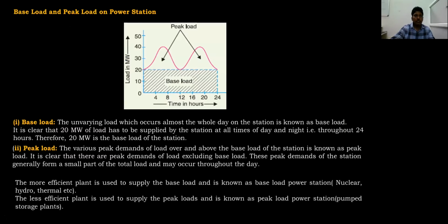And next we are coming to base load and peak load power plants. Base load on a power station means the unvarying load which is there from 0 to 24 hours in a day. For example, here from 0 to 24 hours we have a load curve. This pink color shows the load curve. But up to 20 megawatts, there is always 20 megawatts of load from 0 to 24 hours. This is called the base load. At any given time in the power system, there is a minimum of 20, so it is called the base load.